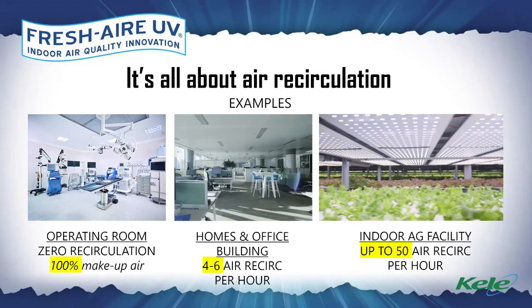And a good example is the next example, which is probably the majority of the applications you're going to address. So for office buildings, for schools, for shopping malls, we don't bring in 100% makeup air. Typically, we recirculate, and we're looking at about 4 to 6 air recirculation rates an hour. So if we don't deliver that lethal sunburn on that first pass, by the second, third, fourth pass, we will achieve that accumulation of the dosage to effectively address the biologicals in about 30 minutes to an hour. So it really is having that understanding of what the customer wants. If you want to have that high log reduction on a single pass, we can deliver that. Of course, you're going to need more UV to achieve it because it's a question of dosage requirements. But if we do enjoy air recirculation rates and we do not have to have that critical air quality, then certainly having a different format UV system is the way to go.